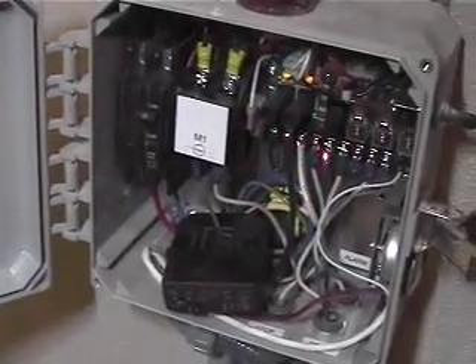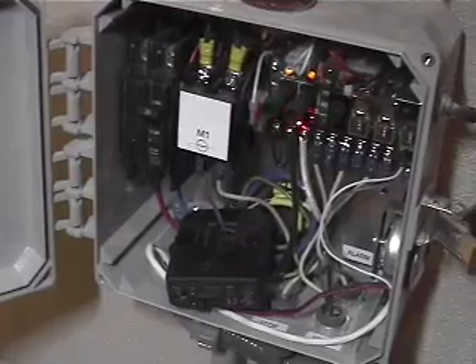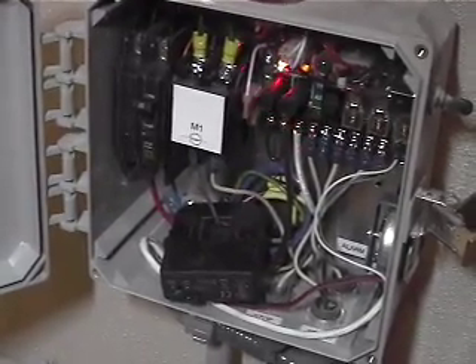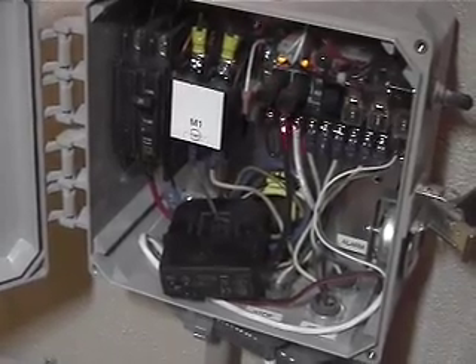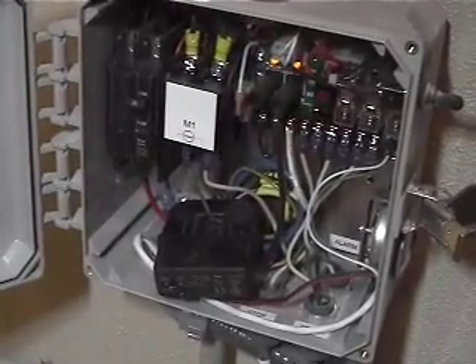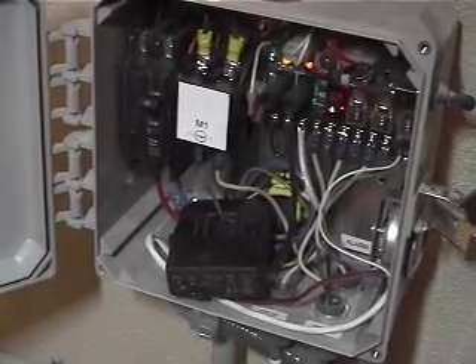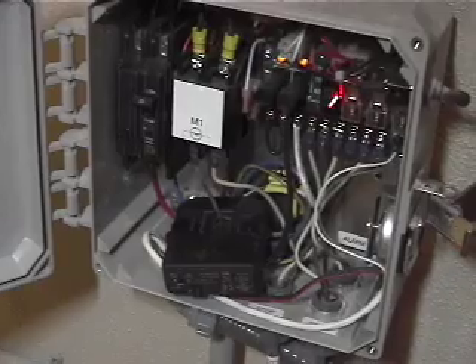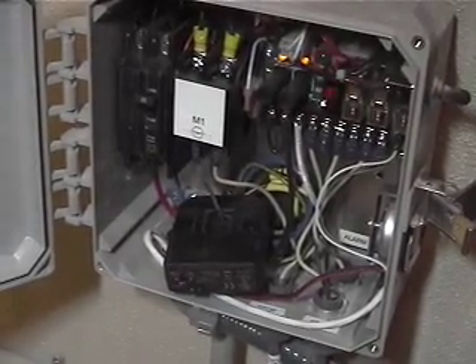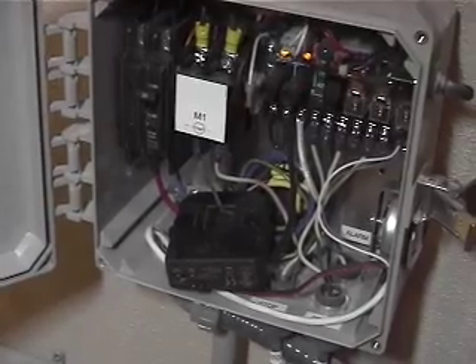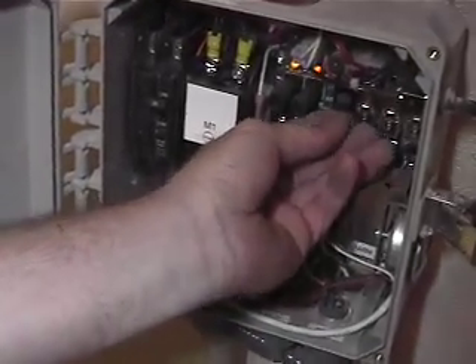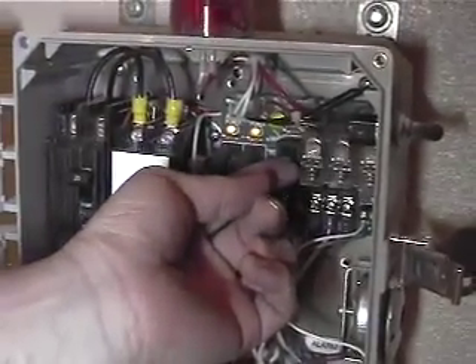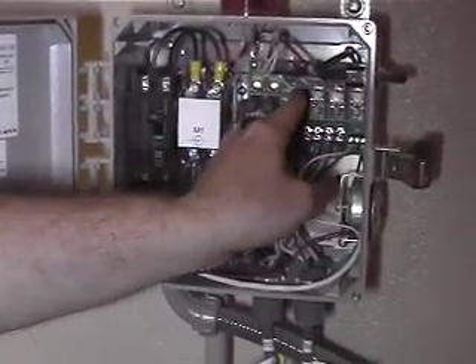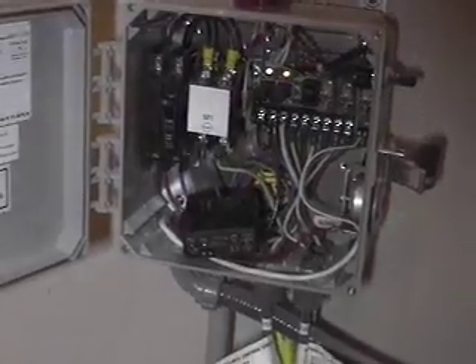This is our control panel here. We've got this LED lit up to let you know that we have power to this board. This LED is lit up to let you know that we've got power to the alarm circuit. This switch right here is a 3-position switch. Right now it's in auto, so if those floats were to come on, it would kick the pump on. If you needed to manually pump the system out, you can flip this switch to hand, which would just be all the way up. And that's pumping out the system. Middle is off, all the way down is auto. And that's really about all that we've got to this.